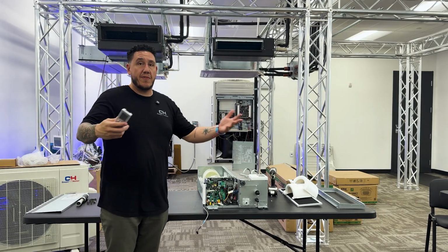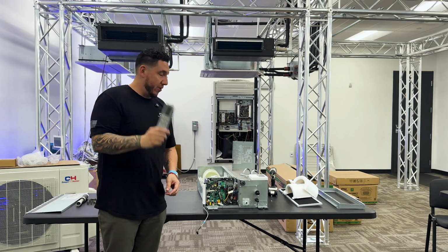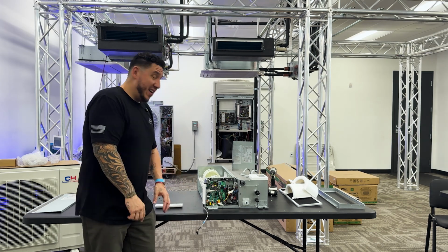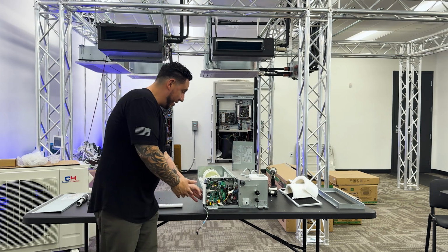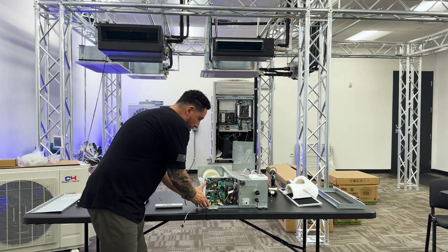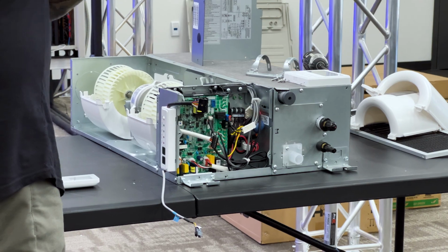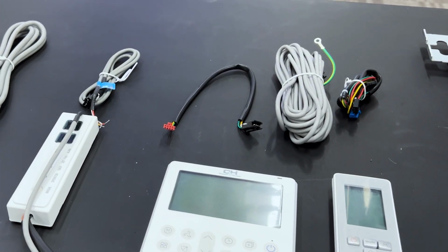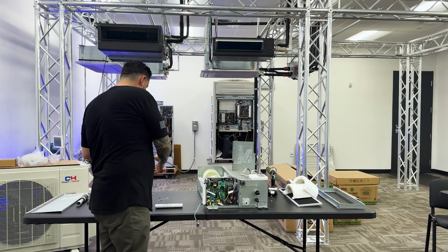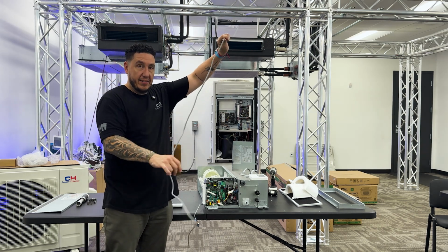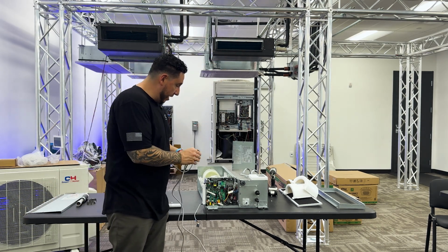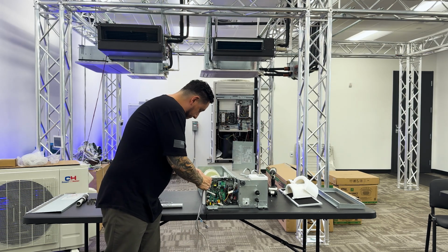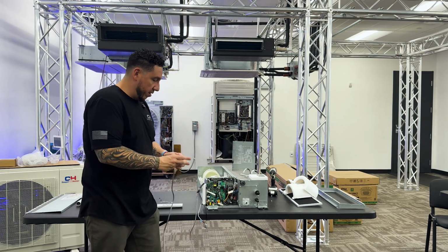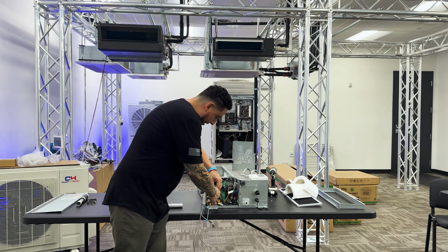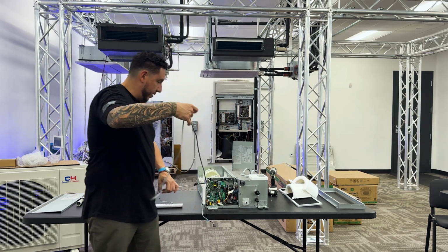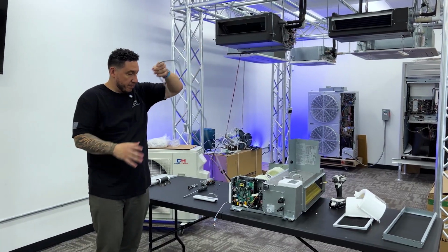Now, this unit's installed. If a technician has to come back and service it with the wireless remote, they could enter engineering mode. Now, if this is installed in a crawl space or an attic, this is not the easiest install to get to. So what we did provide, we have an extension that comes included with the kit, so they could extend the distance between the unit and that sensor. So now I could connect this to my sensor on one end, have this installed in another part of my crawl space or attic, and now I still have the ability to connect to that sensor with plenty of space.